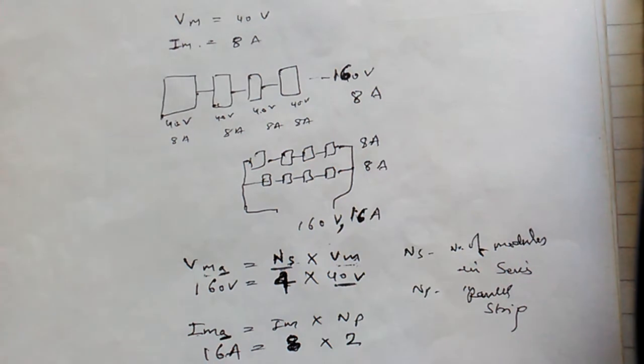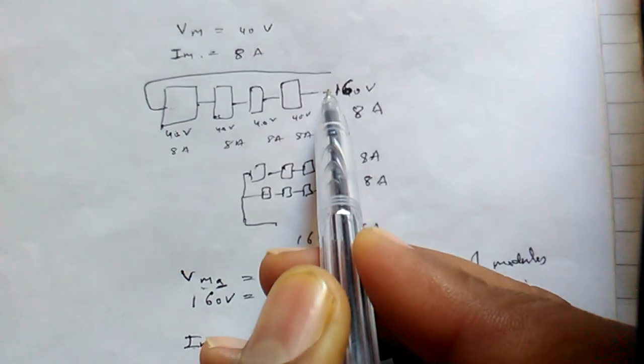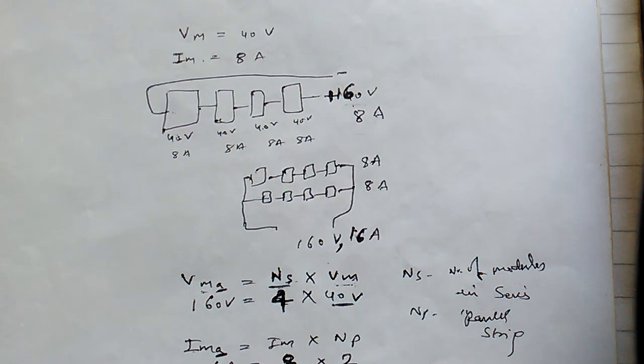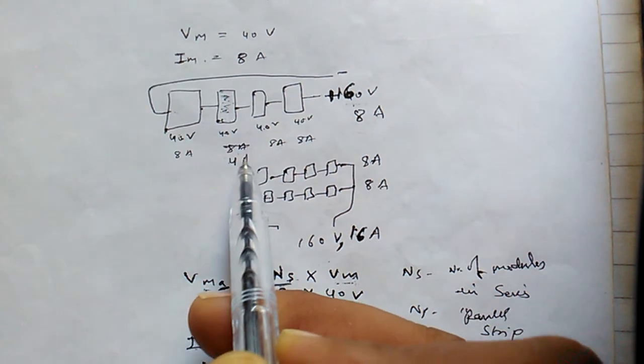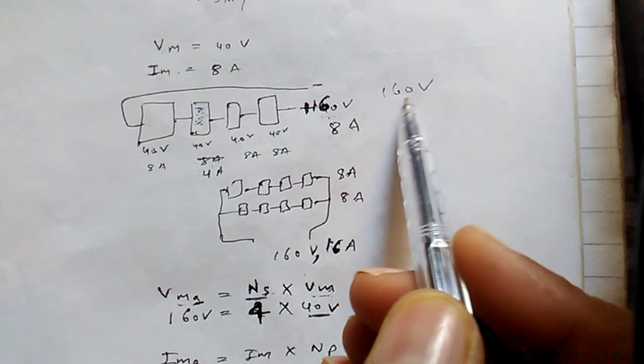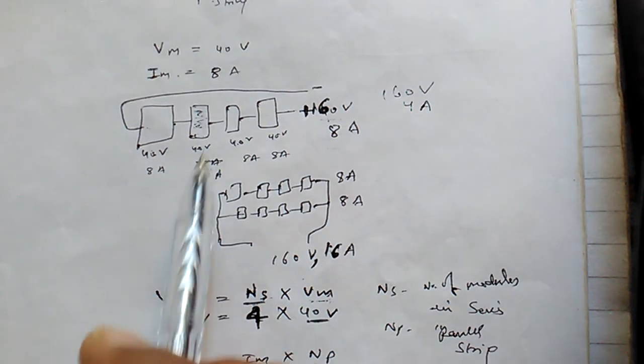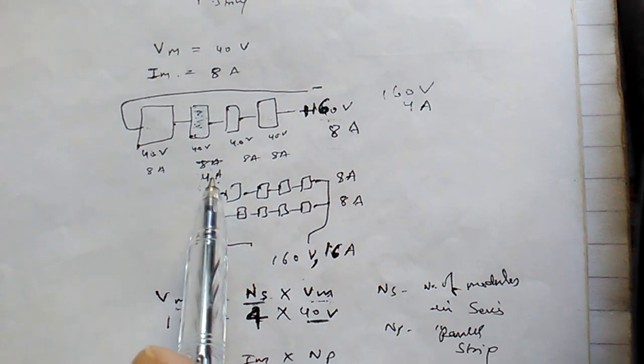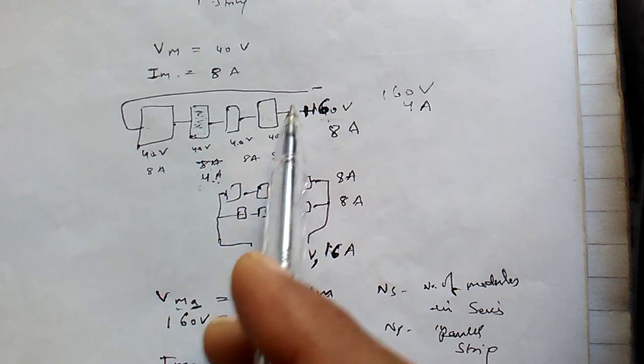The positive and negative terminals give 160 volts and 8 ampere from the string. However, if there is shadow on one module and it provides only 4 ampere instead of 8, the output of the string becomes 160 volts and only 4 ampere, because in a series string the lowest current — 4 ampere — limits the output.